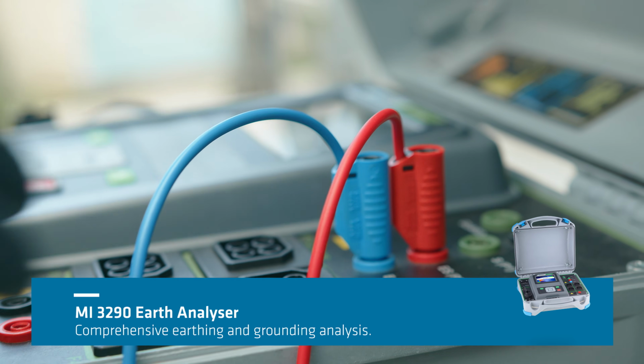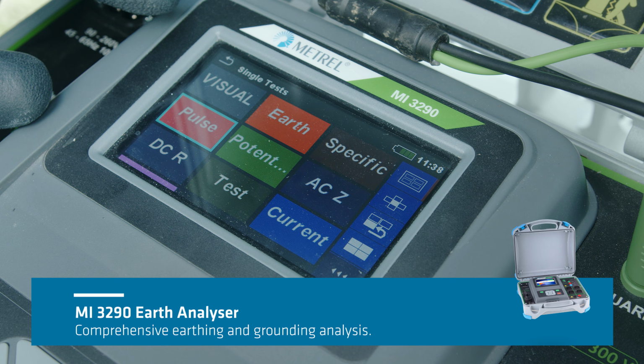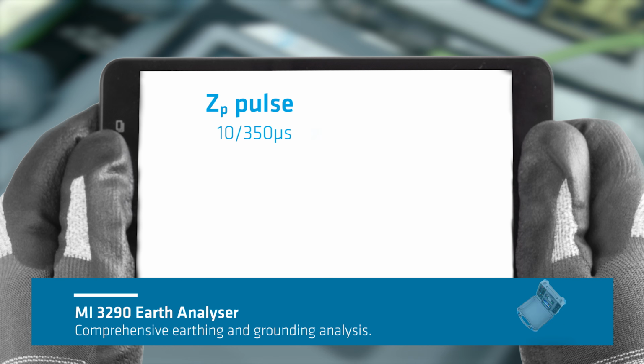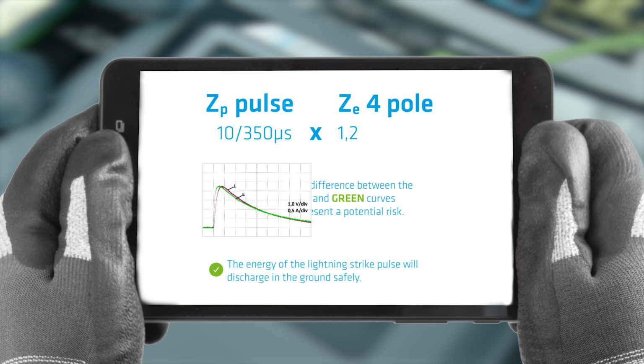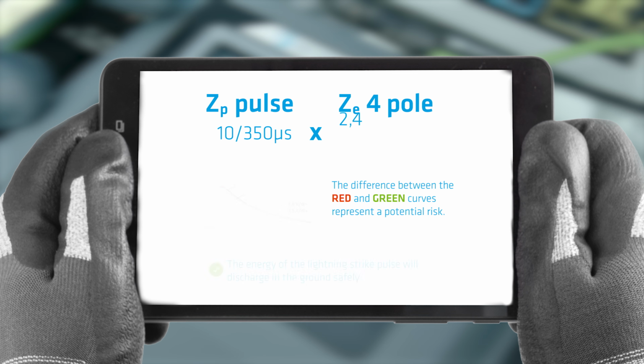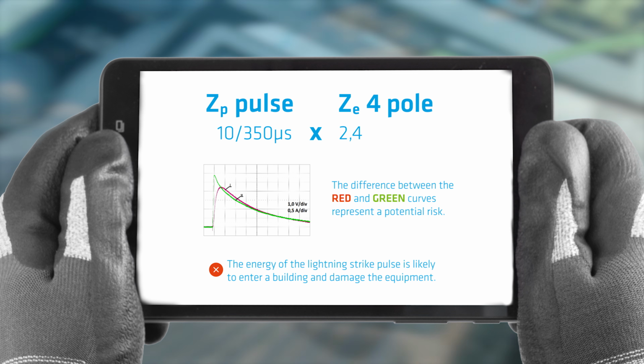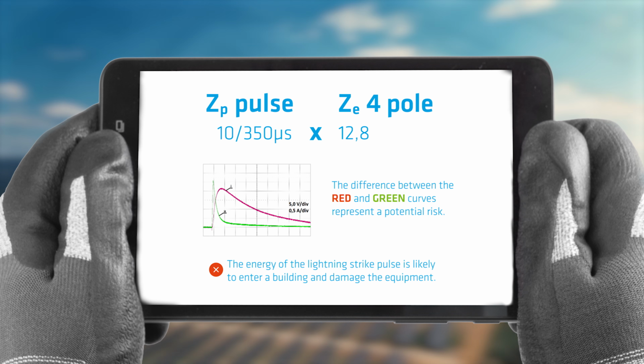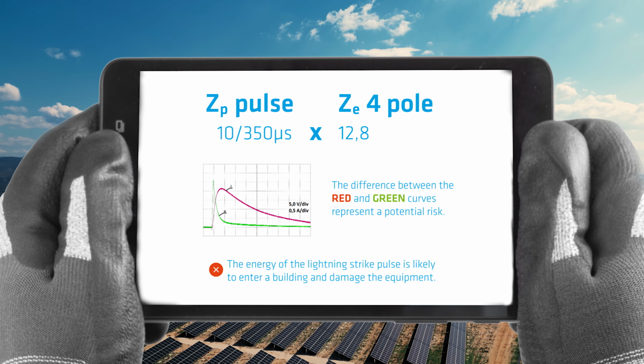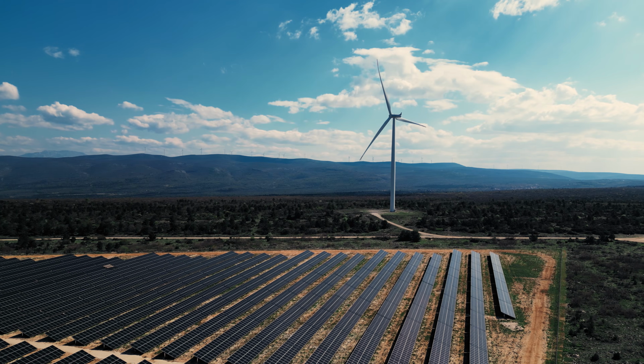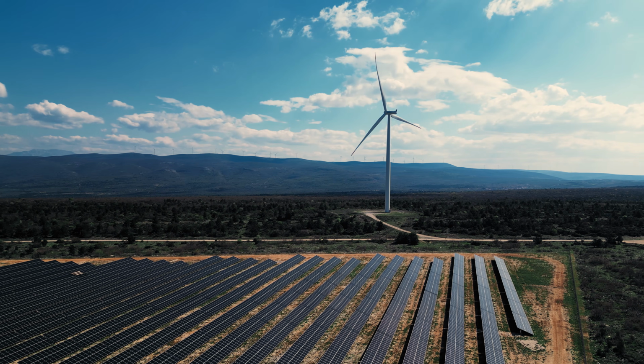For a more comprehensive analysis, the MI3290 Earth Analyser can be used. More precisely, the pulse impedance measurement evaluates grounding quality in situations involving lightning strikes, transients, or surges. The tester also supports low-frequency 4-pole earth impedance, making it an ideal tool for large-scale earthing and grounding assessments of wind turbine farms.